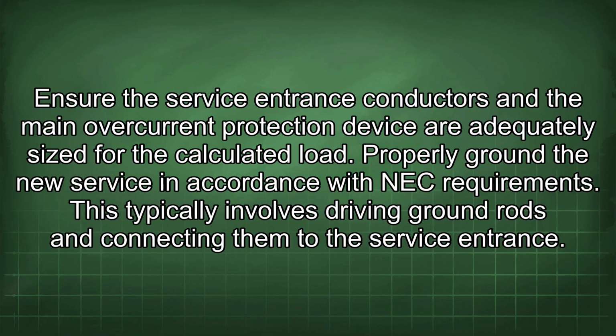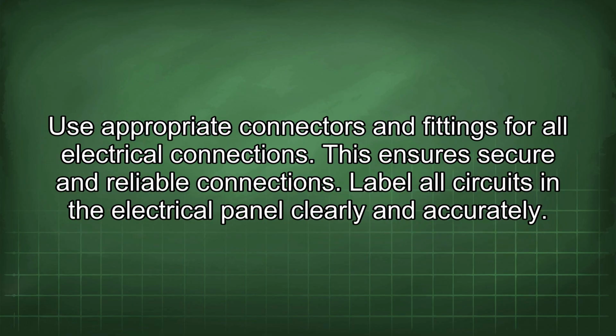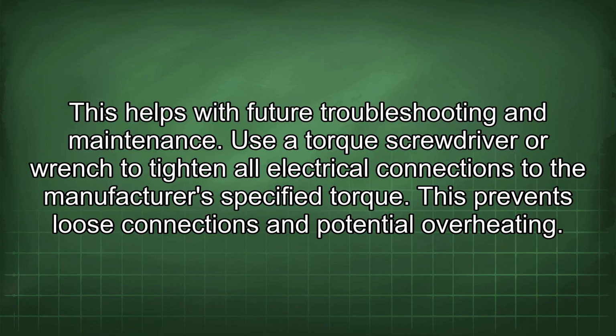Properly ground the new service in accordance with NEC requirements. This typically involves driving ground rods and connecting them to the service entrance. Use appropriate connectors and fittings for all electrical connections. This ensures secure and reliable connections. Label all circuits in the electrical panel clearly and accurately. This helps with future troubleshooting and maintenance. Use a torque screwdriver or wrench to tighten all electrical connections to the manufacturer's specified torque. This prevents loose connections and potential overheating.